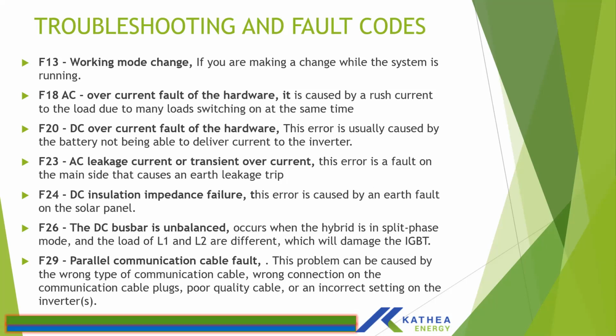And then the AC leakage and transient overcurrent. This is usually caused by earth leakages and all that. You can actually get this fault when you are running a generator on the Aux port. When you have multiple inverters, you can get this fault as well.